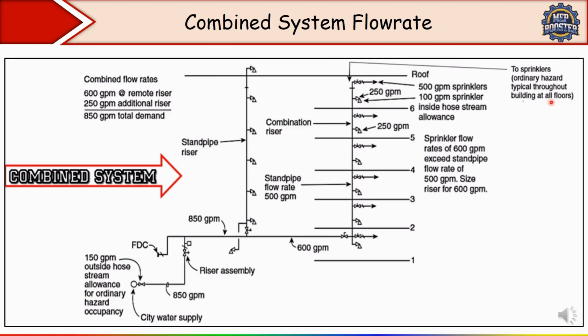Second, here we have an ordinary hazard. You can see it is given clearly here, it is written. So suppose your building comes under ordinary hazard, so at that time, see this diagram represents the flow rate distribution for a combined system and sprinkler designed for ordinary hazard occupancy, okay.